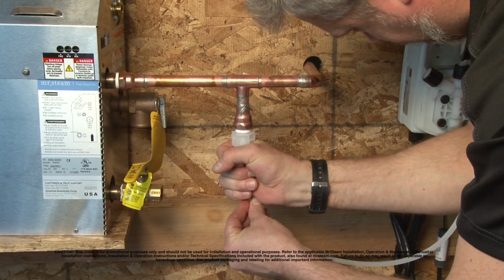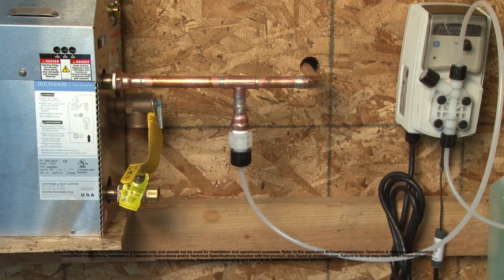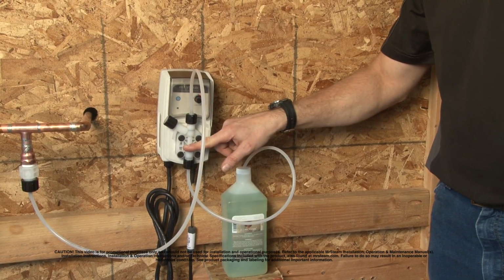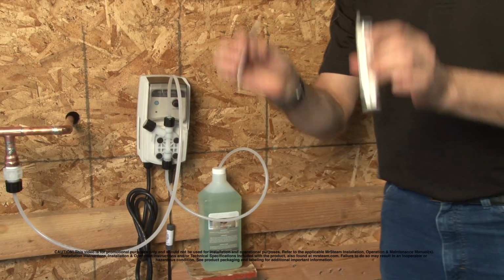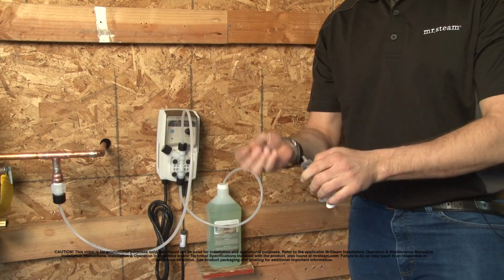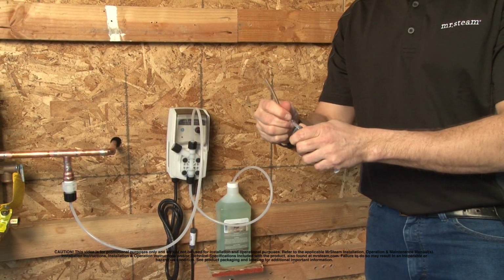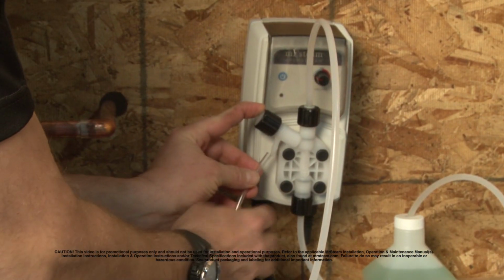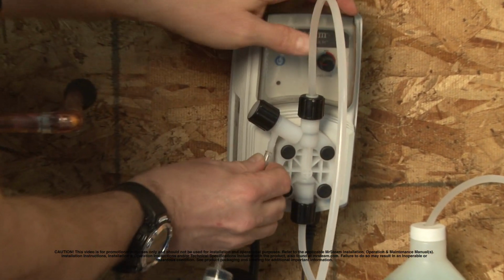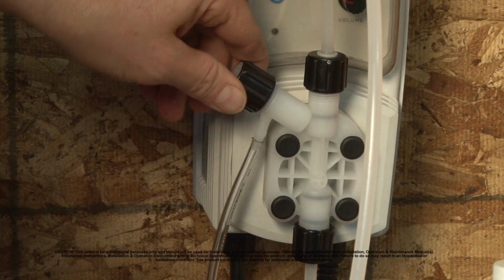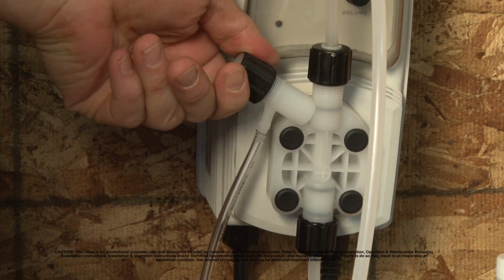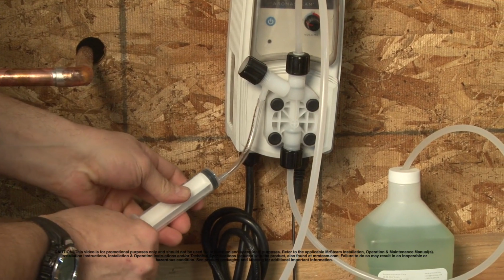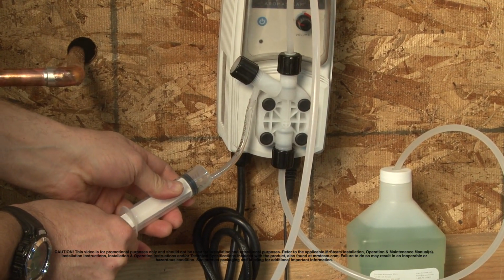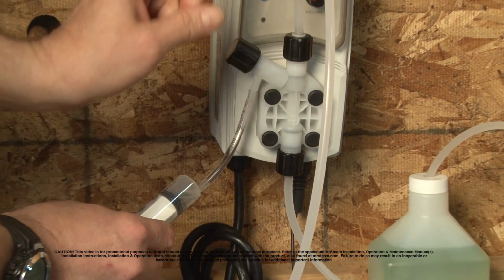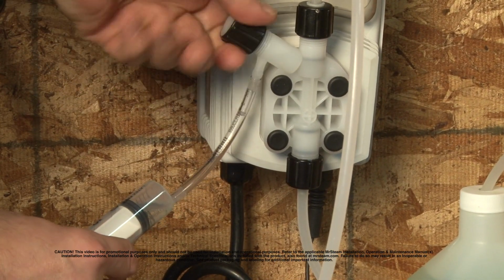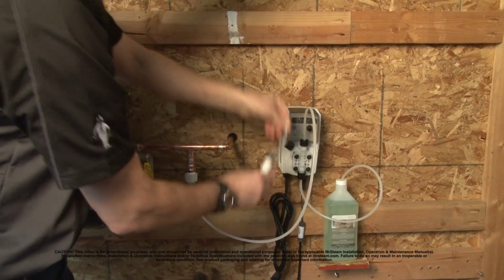Now, in order to get the oil from the bottle to the pump, we use this, an injector and flexible tubing. We attach the injector into the flexible tubing and the flexible tubing to the angled primer valve on the pump. We open the priming valve by turning it here. We pull the plunger of the injector until oil starts to enter the tubing and the injector. Then stop pulling, close the valve, and remove the injector.